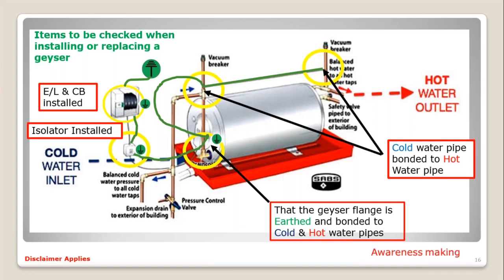So in this installation, when we're replacing a geyser, these are the items we need to look out for. That there is an earth leakage and circuit breaker installed, which will be at your main distribution board. Where there is an isolator installed, that will normally be within arm's reach of your geyser or heat pump that you need to isolate. Then you need to make sure that the component is earthed, where the earth terminal is supplied to the geyser, and that from that earth terminal your hot and cold water pipes are bonded together. You will see the illustration between the two, where the earth wire is connected to the bonding and connected to the hot and the cold water pipe.